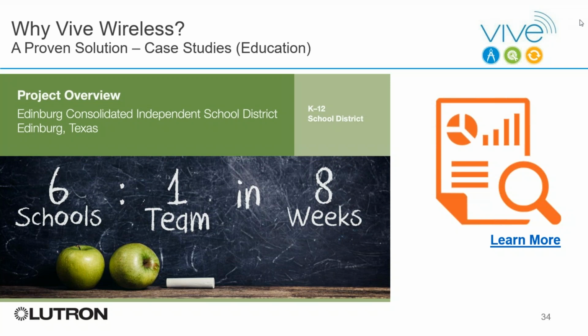So some other examples that I love to share about Vive in terms of making it real and showing the actual value in a real road test. This was a job in the Edinburg Consolidated Independent School District in Texas, where they had a bit of a thermal issue with the lights in their space. Basically, they had put in some lower cost TLED solutions that weren't built to the highest quality standards and were spontaneously combusting. So you had 6 different elementary schools with all these TLEDs really not having a good day. So obviously they had fire marshals stationed there and everything like that. So they had to very quickly renovate this school to eliminate this issue.